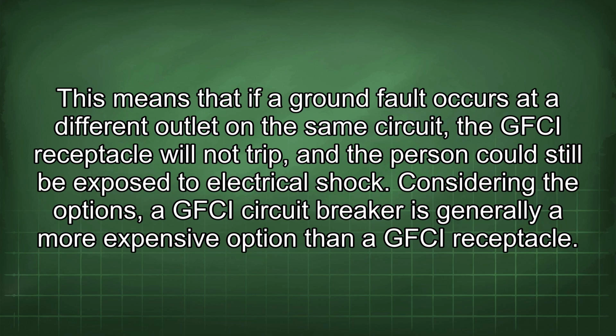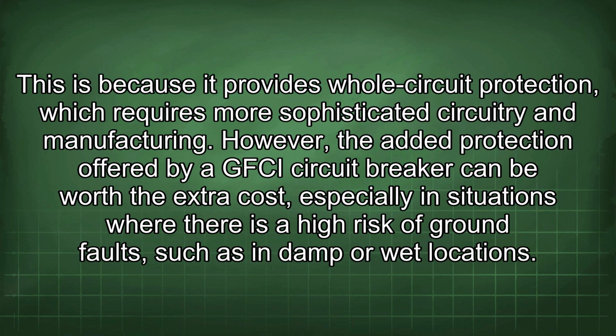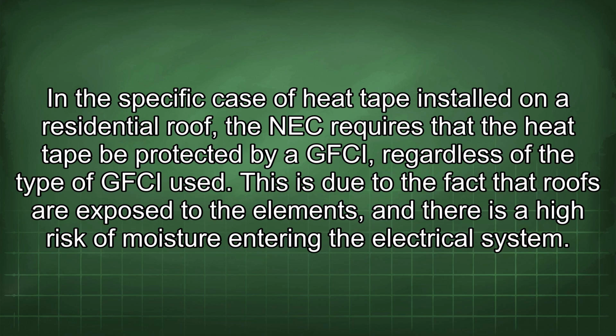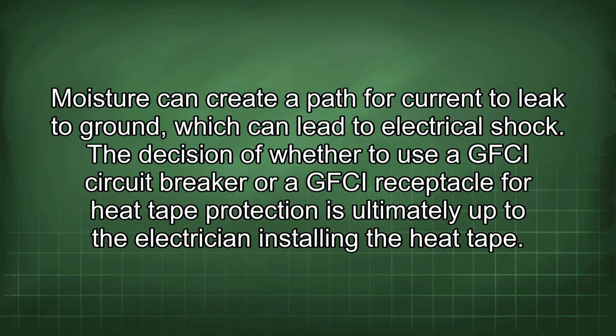Considering the options, a GFCI circuit breaker is generally a more expensive option than a GFCI receptacle. This is because it provides whole circuit protection, which requires more sophisticated circuitry and manufacturing. However, the added protection offered by a GFCI circuit breaker can be worth the extra cost, especially in situations where there is a high risk of ground faults, such as in damp or wet locations. In the specific case of heat tape installed on a residential roof, the NEC requires that the heat tape be protected by a GFCI, regardless of the type of GFCI used. This is due to the fact that roofs are exposed to the elements, and there is a high risk of moisture entering the electrical system. Moisture can create a path for current to leak to ground, which can lead to electrical shock.